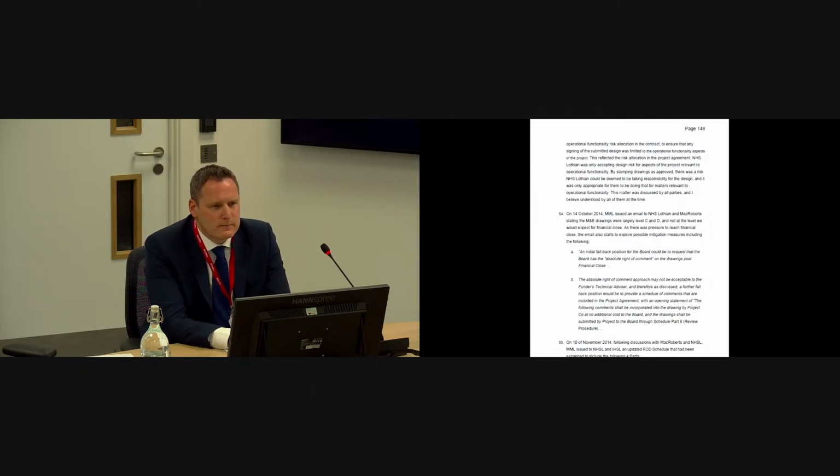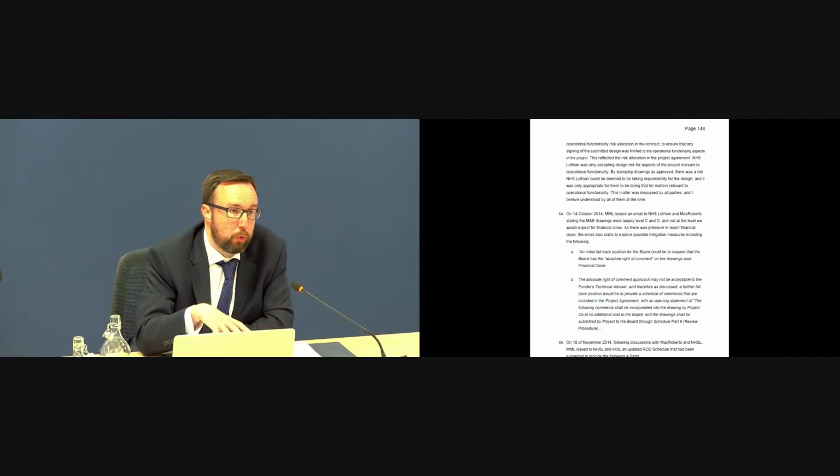So again, probably not known about at the time, but say you were working on a project of this nature now for a different hospital facility, and someone simply said we're going to use room data sheets produced with the ADB system, would you have concerns about that if there wasn't going to be a detailed review of those room data sheets? Yes. And just, it may be obvious, but why? Yeah, there are known issues with the environmental characteristics in the ADB sheets, so there needs to be a robust methodology now for developing them. You use your template ADBs as a starting point, and then you develop it in consultation with various stakeholders.